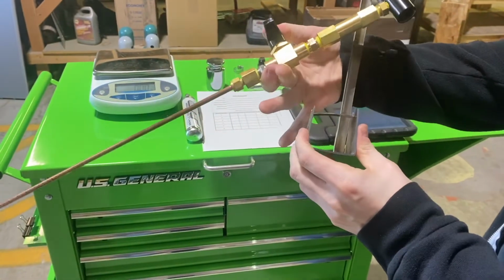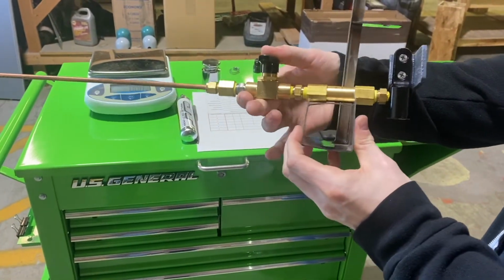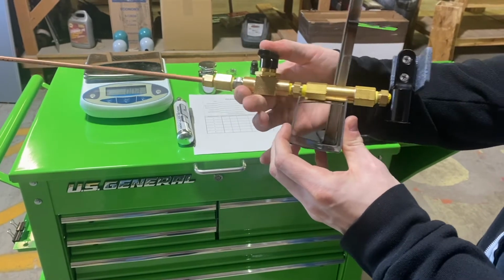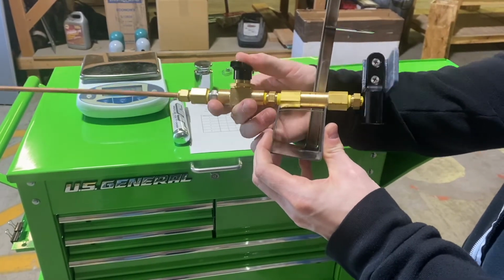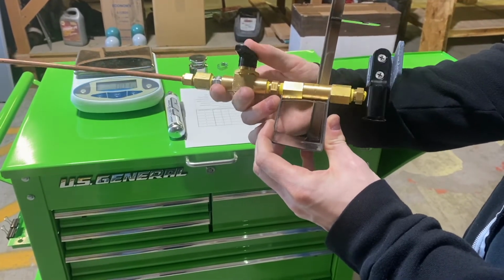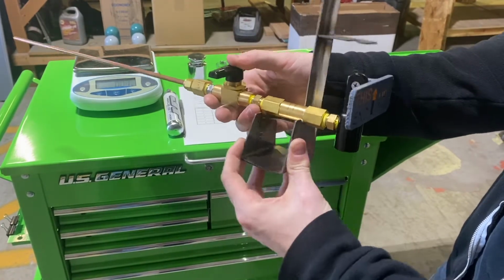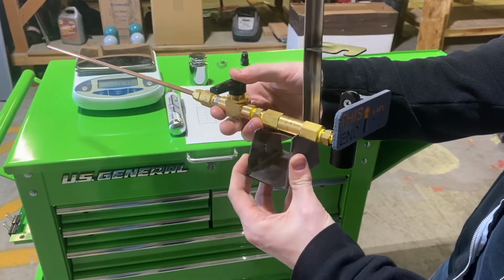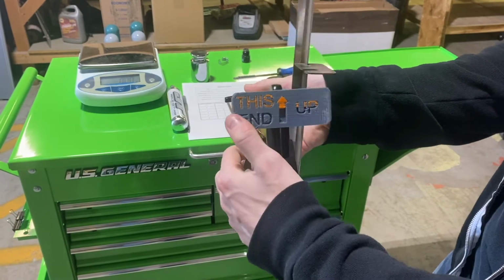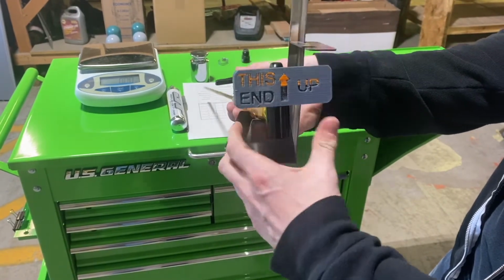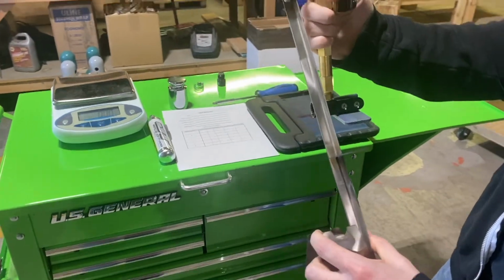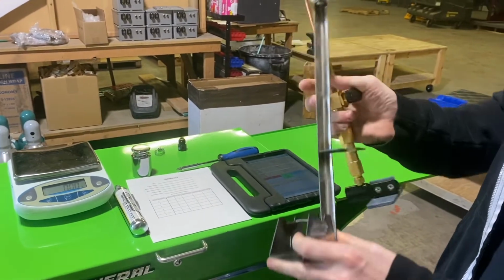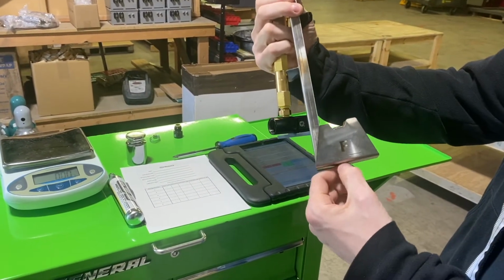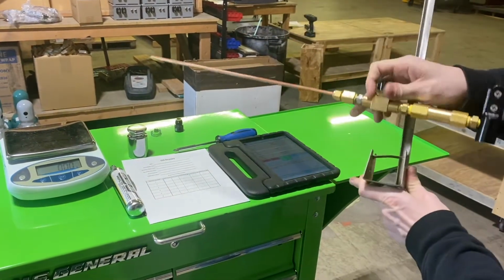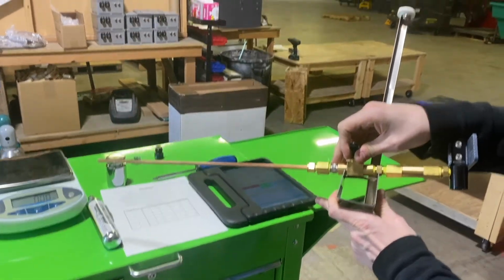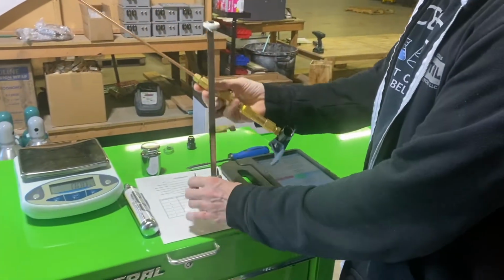We're going to place the release device right over here, and you can basically position it anywhere here. It probably won't have a very level setting. Just put it there and get as close to straight up as you can. We're going to want the label facing up, pointed toward this RFID tag. And we're also going to want the F right here facing the same way that the nozzle is facing. All right, so I'm going to do that right here.